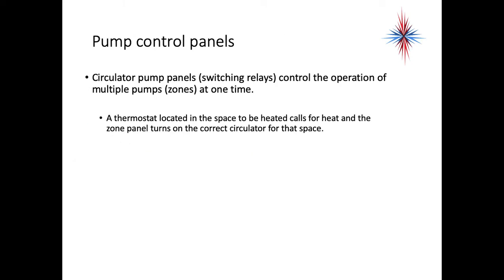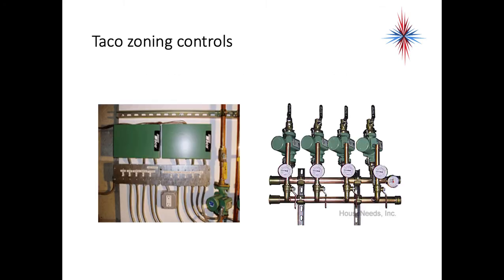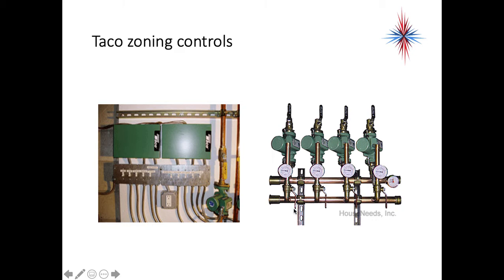Circulator pump panels, like switching relays, control the operation of multiple pumps at one time. A thermostat in each space calls for heat, and the zone panel turns on the correct circulator for that space. There are also configurations with zone valves rather than circulators. This is an example of a Taco zoning control where each switch controls one circulator. In a well-installed system, you can de-energize every single circulator individually without de-energizing the rest of the system.